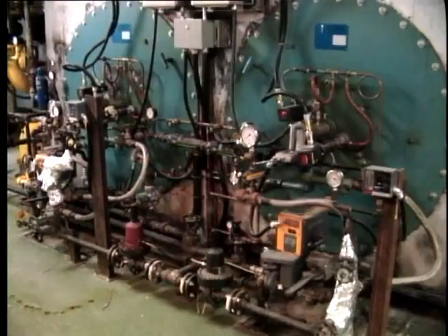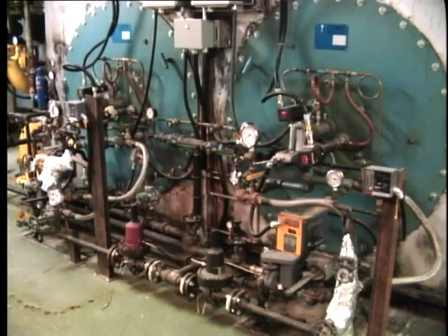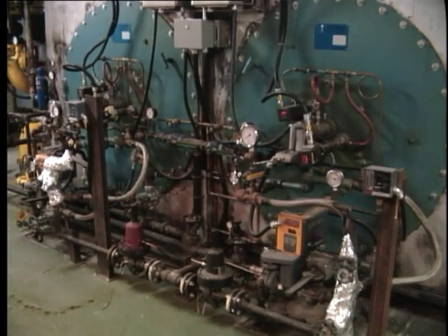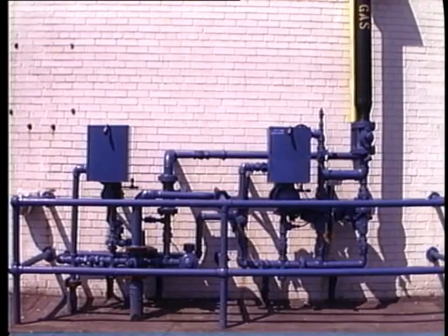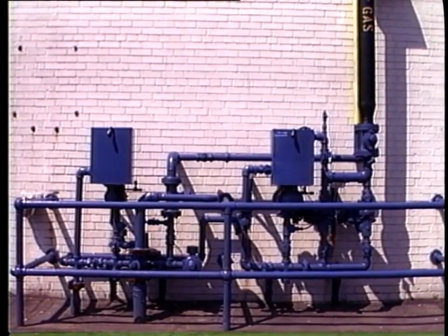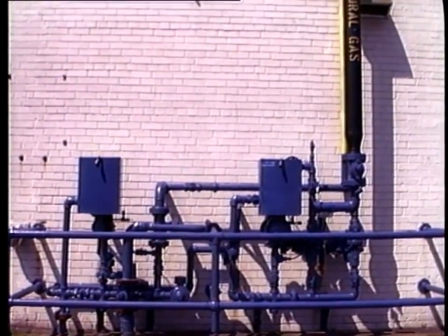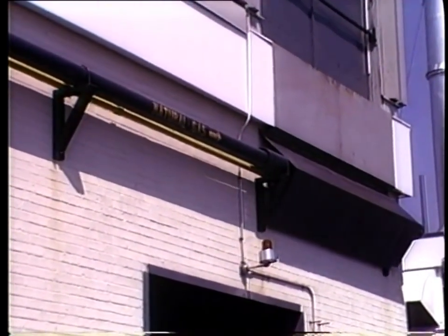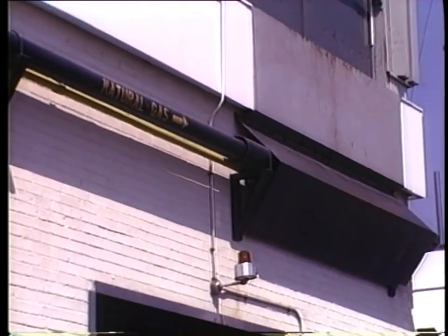popular fuel, natural gas. Firing with natural gas has some similarities to oil firing, and it is certainly the simplest fuel of all to burn. In most installations, the gas requires no preparation at all, as it is delivered under pressure directly from the supplier. Therefore, no storage facilities are required. The supply is metered at the incoming station, where its pressure is reduced to that suitable for the boiler.